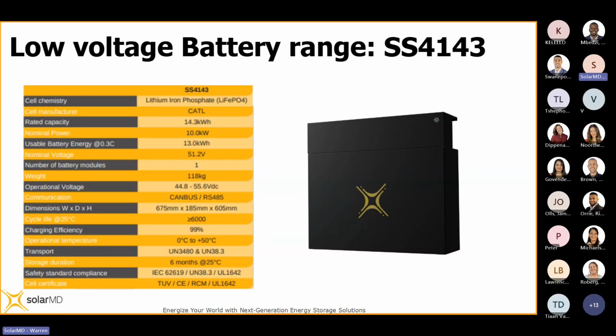Batteries that are older than a year, maybe 2 years older, and have done a lot more cycles, the cells build up a higher internal resistance compared to the new battery you might be installing today. So you'll find that the newer battery will counterintuitively discharge faster, meeting the demands of the system ahead of the older battery. Because electricity tends to take the path of least resistance, and you've got this new battery with young, supple cells with low internal resistance, that newer battery is going to deliver the power sooner. So you'll find that the newer battery will discharge quicker as a result. The older battery will ultimately catch up and take over more and more of the load as both batteries reduce in their state of charge.